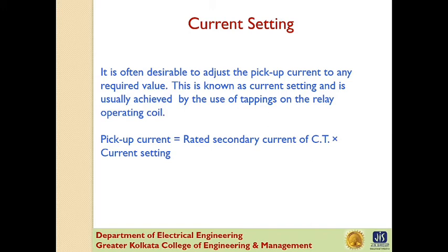The values assigned to each tap are expressed in terms of percentage full load rating of the CT with which the relay is associated, and represent the value above which the disc commences to rotate and finally closes the trip circuit. Now, pickup current is equal to rated secondary current of CT times current setting.